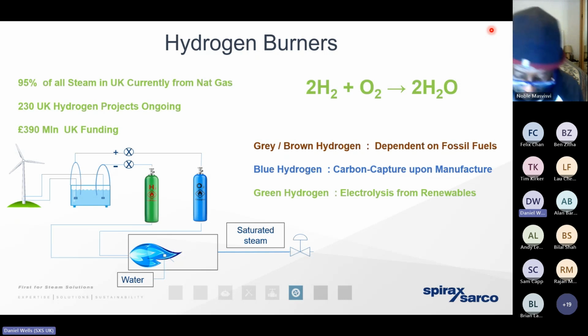So in many cases, we can look at our existing steam boiler, we can get rid of the natural gas burner, we can retrofit a hydrogen burner, cap off the flue, there aren't going to be any emissions, and we can generate steam. All we've done is change the primary energy source. The water treatment, the boiler, the distribution pipework, the safety features, the process, it remains exactly the same. Now, we're not combustion engineers at Spirax Sarco, but we do know that the only way a hydrogen burner is really going to be viable is if our client has got a reliable source of green hydrogen on site, if they're producing their own hydrogen locally. If they're reliant on grey hydrogen or blue hydrogen, they can't truly say that they've decarbonized their thermal energy.